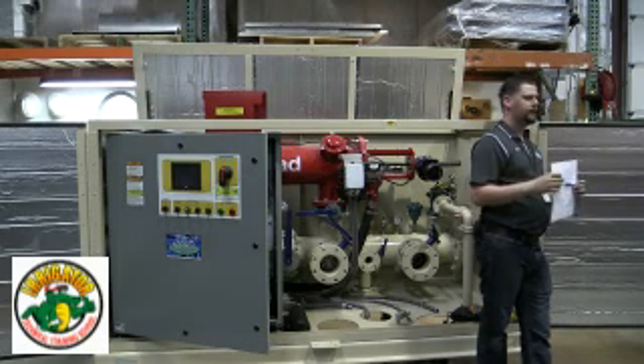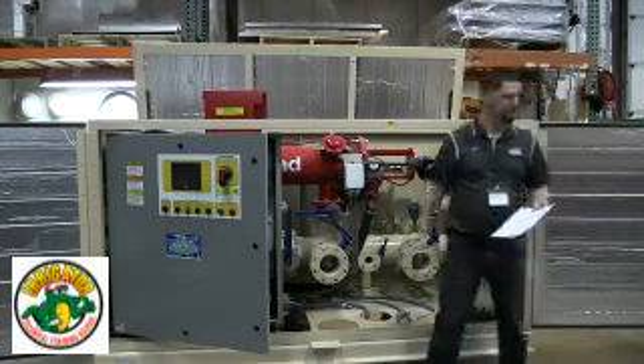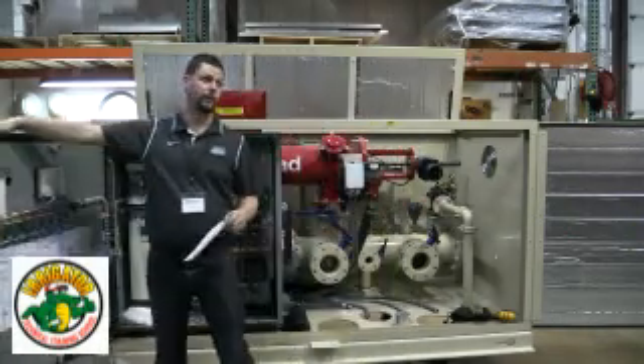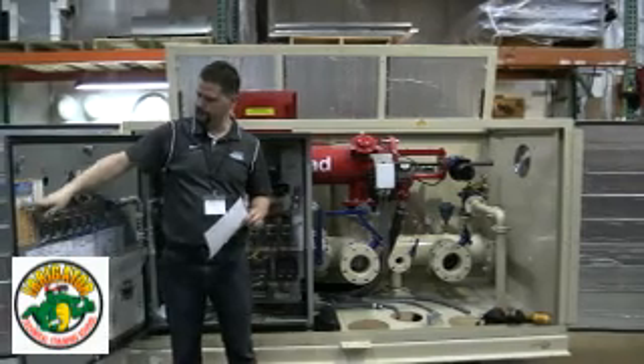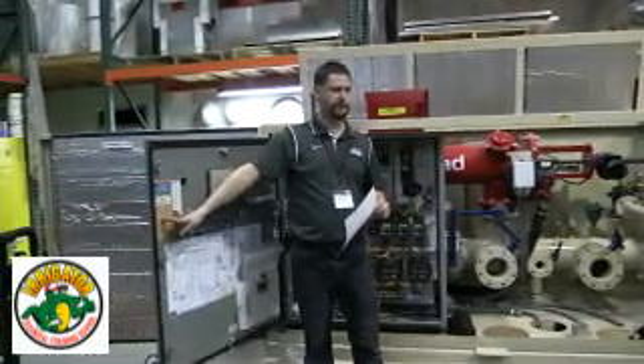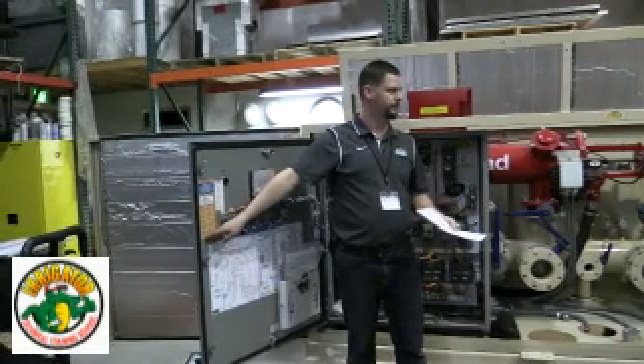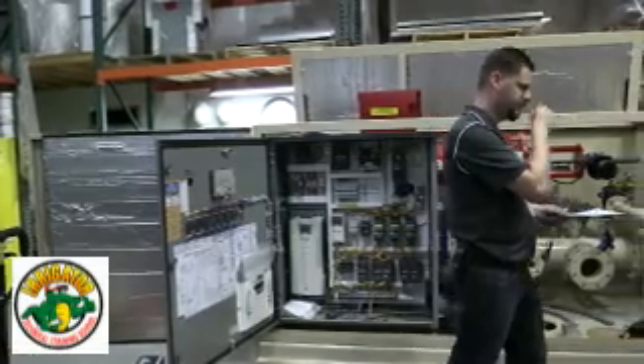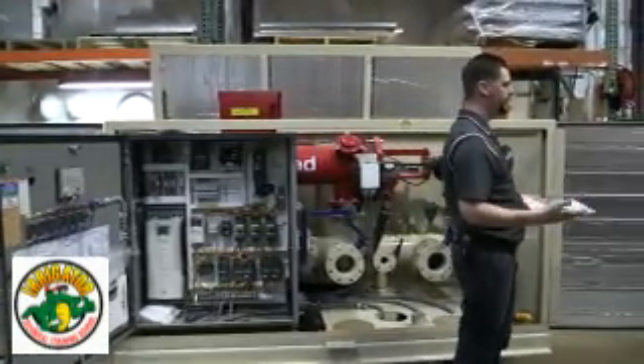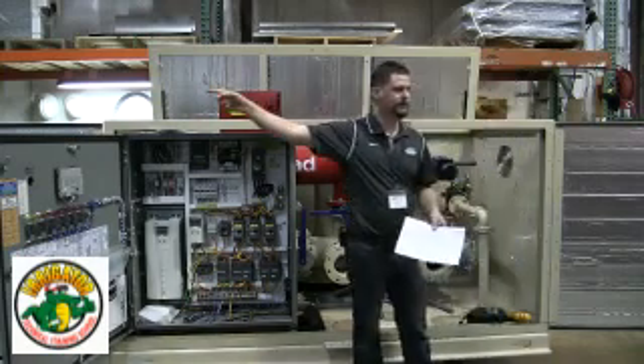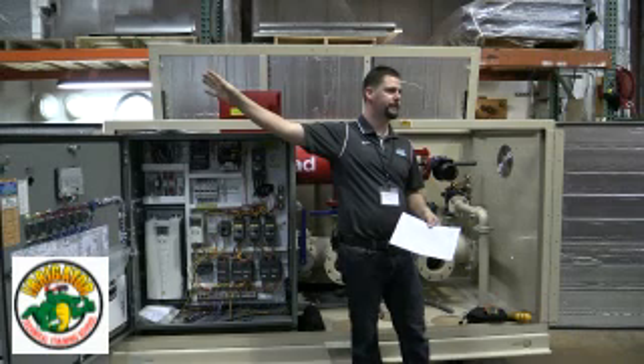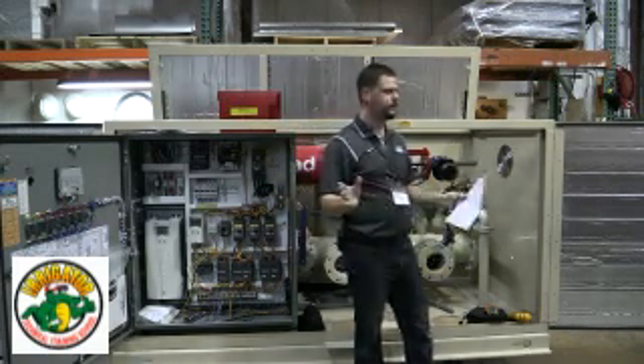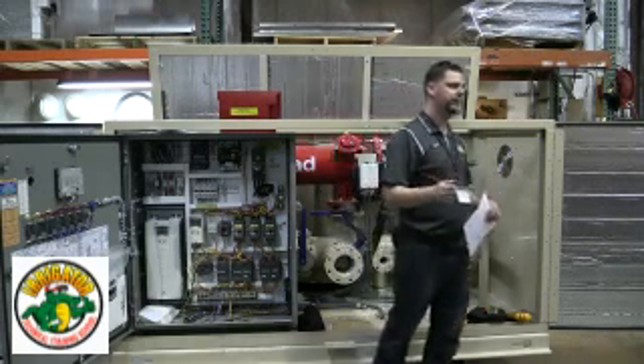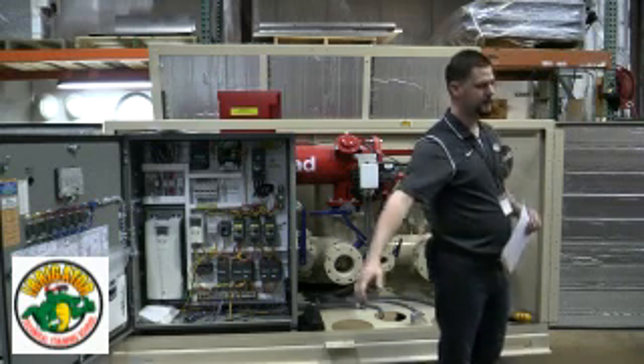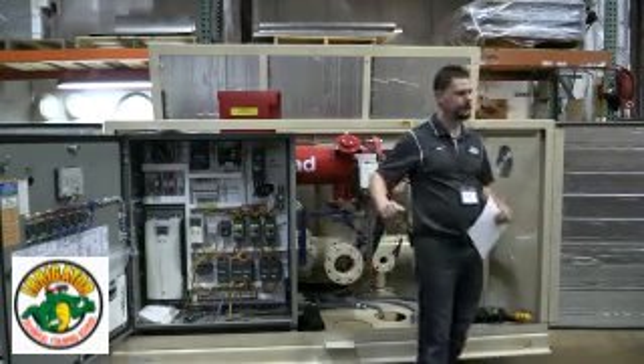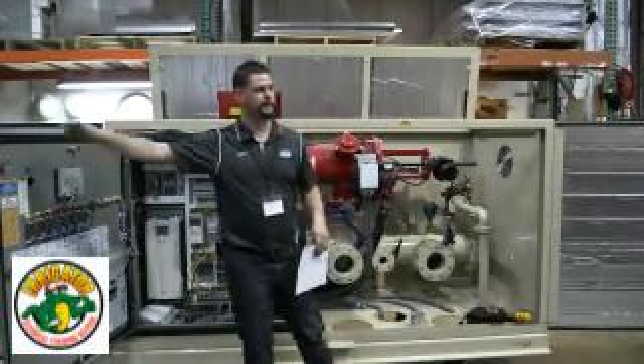Here's your best friend. Yeah, and actually, I'm glad you brought that up because I did overlook this. Almost all of our panels have a spec label, and that spec label includes the design point for all of the pumps when they were brand new. So, back to the flow meter discussion. If you have a flow meter, the best way to test them is have some water turned on, open some valves, give water a place to go. Start each pump individually. Doesn't necessarily have to be in hand, but they need to be going full speed for this test. And then close the pump station isolation valve, just feather it until it gets to the pressure on the design point, and then look at the flow.